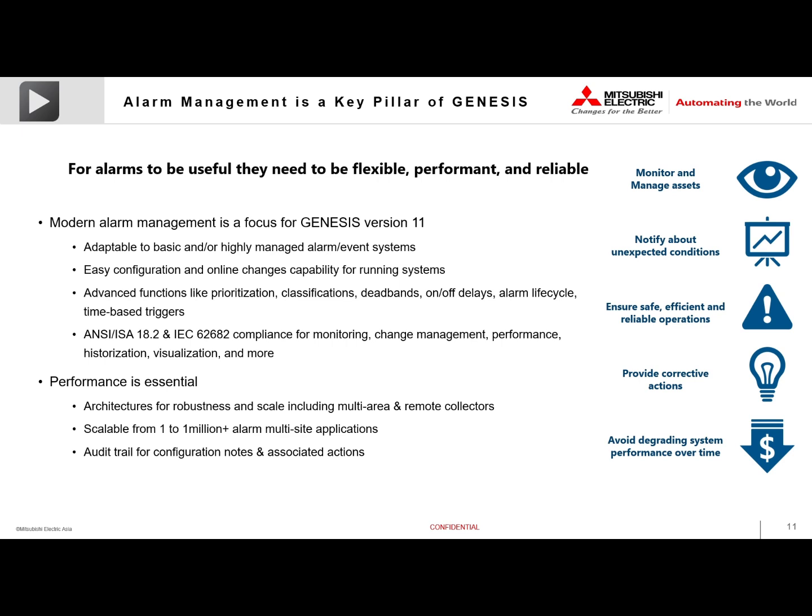So all these flexibilities and additional functions like prioritization, classification, dead bands, all those things are already included inside here. And our alarm server is also compliant to ISA 18.2 and IEC 62682 for the monitoring and change management. And scalability from one single alarm to 1 million alarms and on multiple sites as well, so you can expand.